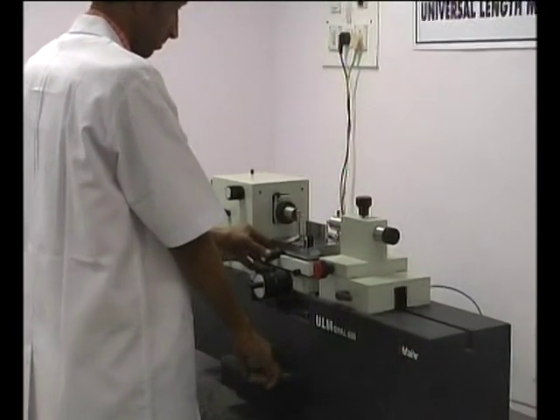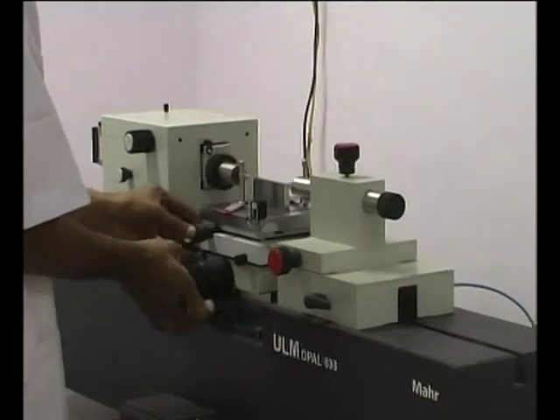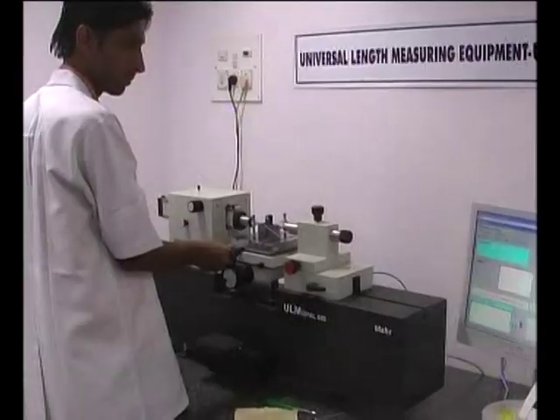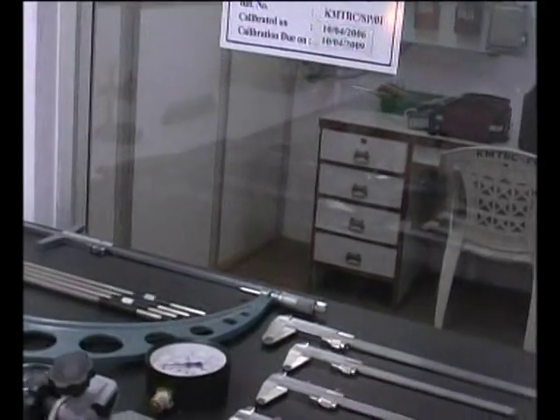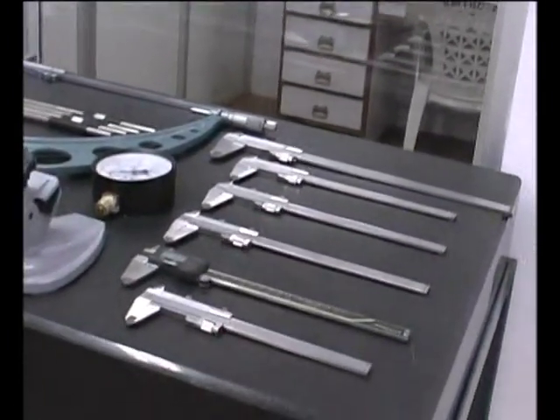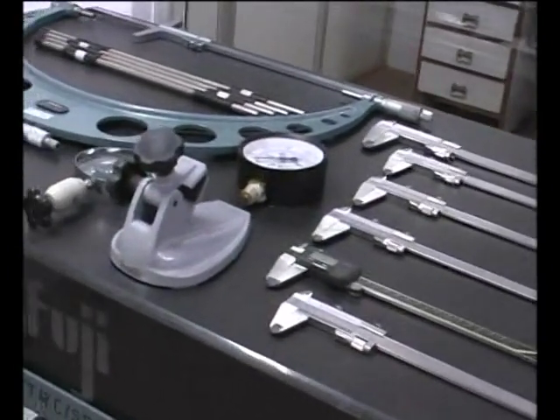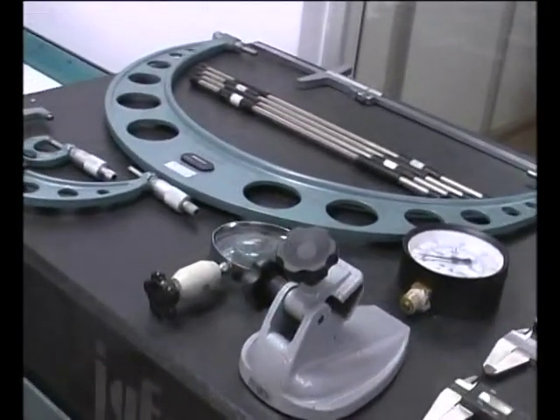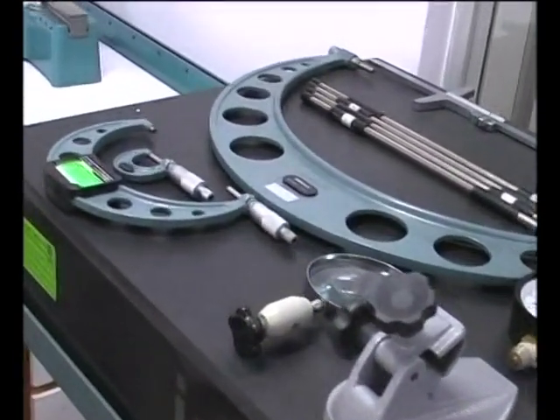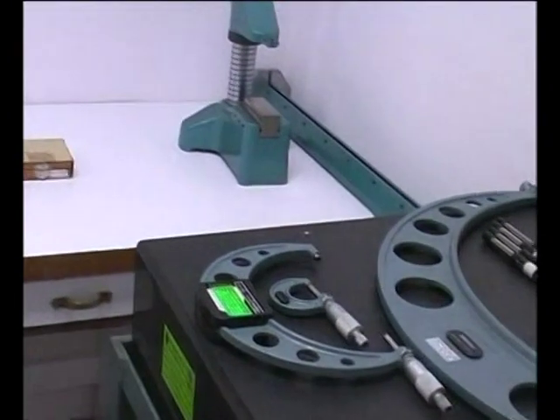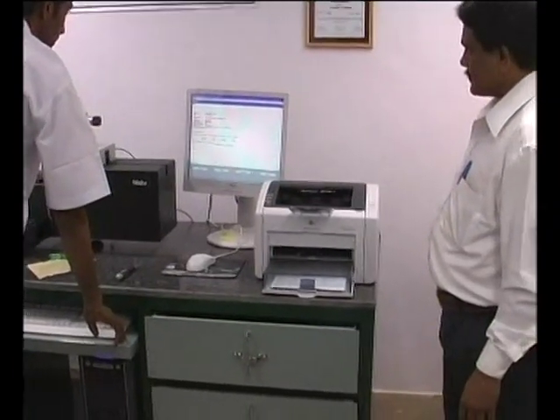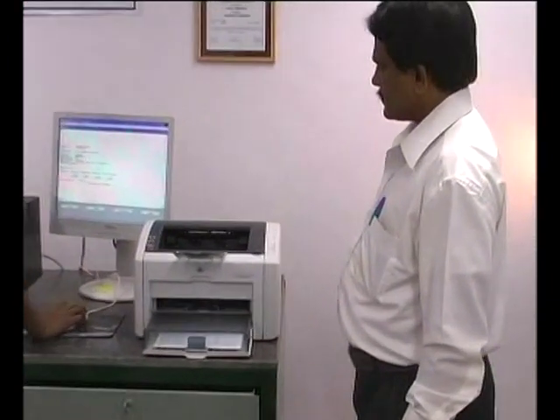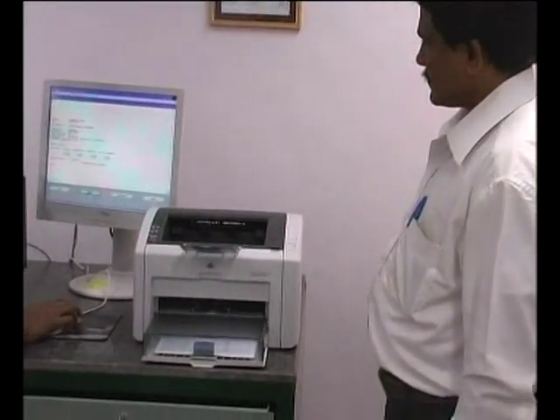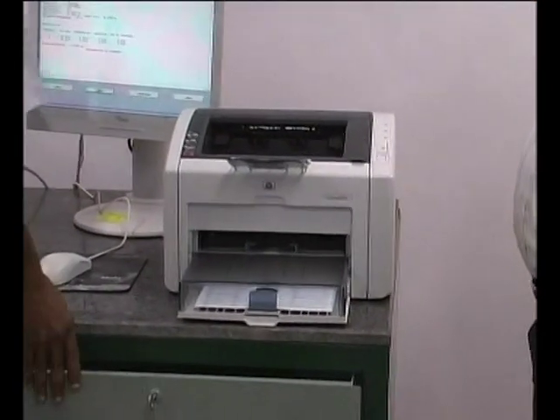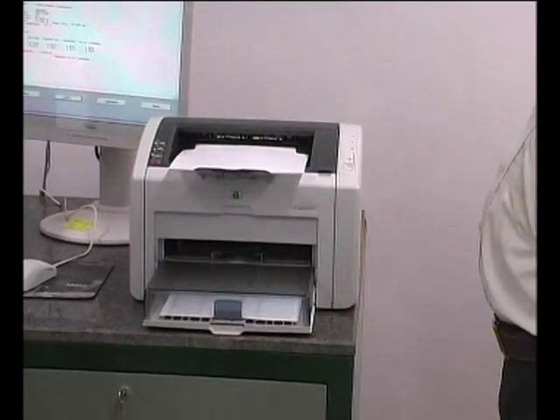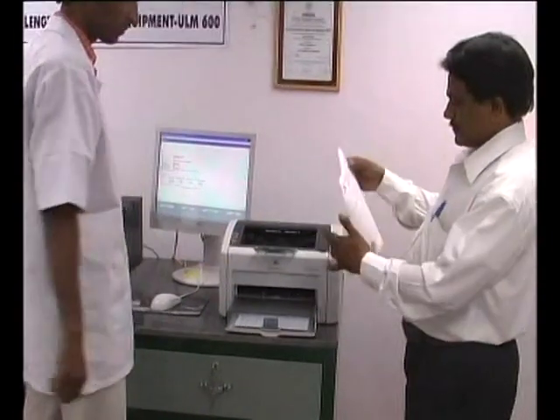This latest technology universal length measuring equipment ULM 600 is very useful to calibrate plain plug gauges, external and internal micrometers, ring gauges, bore indicators, vernier calipers, internal and external thread gauges, dial indicators and also snap gauges. Instruments can be calibrated in this division in the environmental conditions of 20 plus or minus 1 degree centigrade. The certificate will be issued to the customer after the calibration.